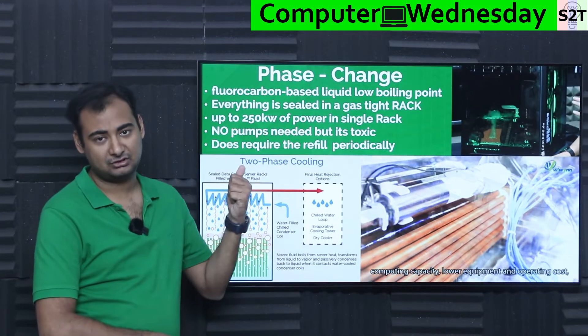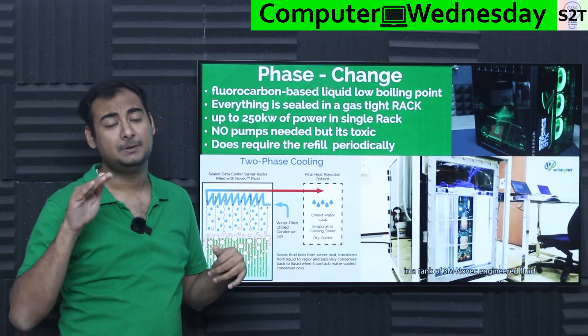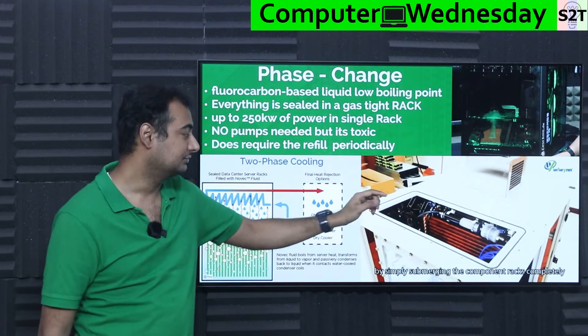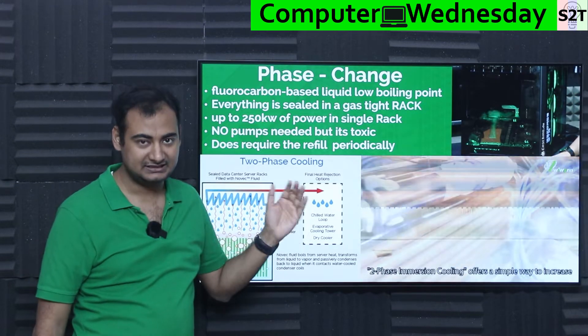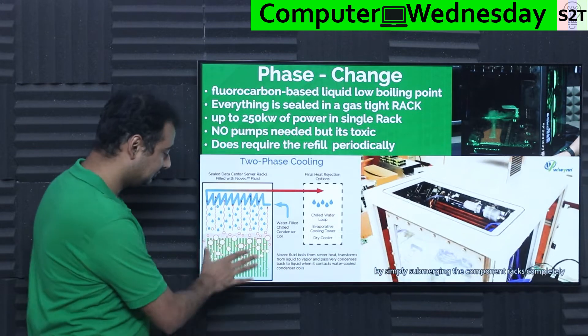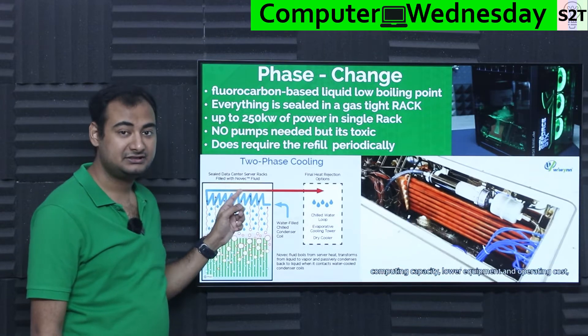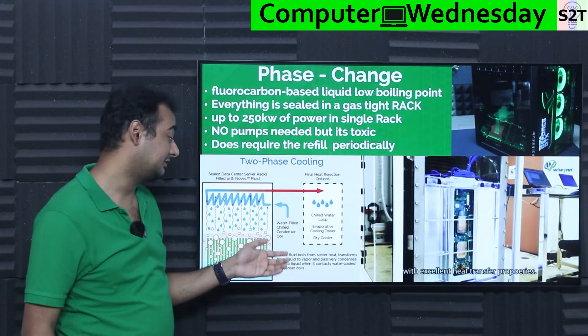There are two approaches to immersion cooling. First option is two-phase: you let the liquid boil. Fluorocarbon-based liquids are used, which generally have a low boiling point — below 50 degrees Celsius they start to boil. You dunk everything and it starts to boil, and the vapor goes to a condenser. Everything happens in one unit — the condenser consists of copper pipes connected to building water, and that building water removes the heat, condensing the vapor back. You can connect it to a chilled water loop, evaporative cooling, or a dry cooler.